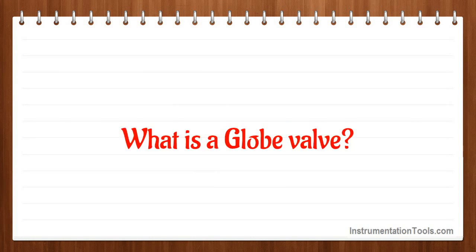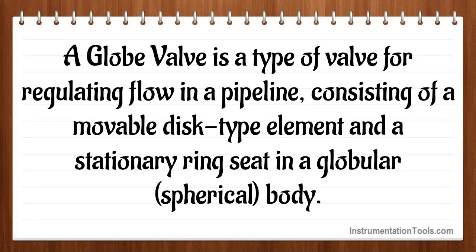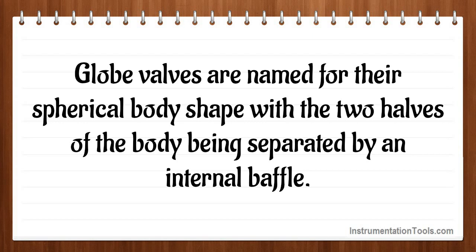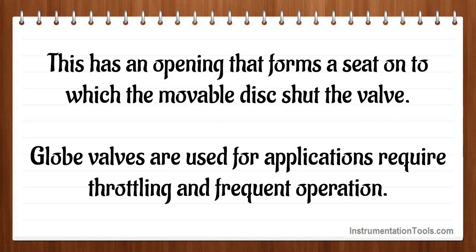What is a globe valve? A globe valve is a type of valve for regulating flow in a pipeline, consisting of a movable disc type element and a stationary ring seat in a globular, spherical body. Globe valves are named for their spherical body shape, with the two halves of the body being separated by an internal baffle. This has an opening that forms a seat onto which the movable disc shuts the valve. Globe valves are used for applications requiring throttling and frequent operation.